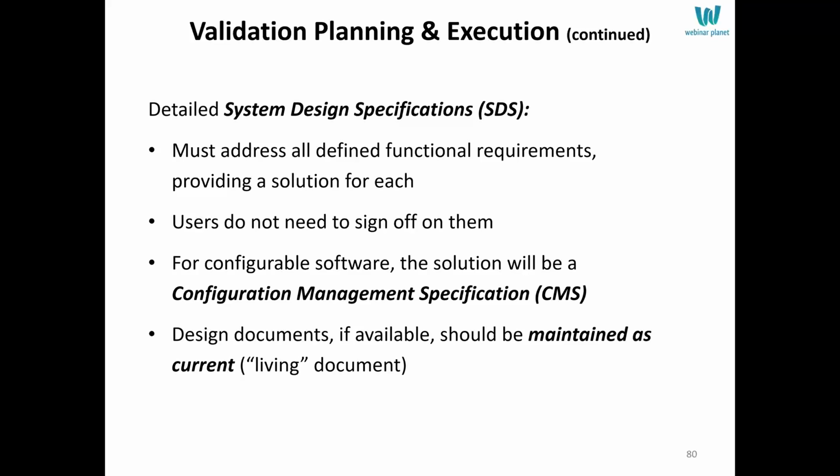But again, you may not have access to these. If the vendor has them, you would want to make sure you state in your validation plan, we asked the vendor, they wouldn't provide these documents. And so by virtue of the fact that once we put the application software in place and test it through OQ and maybe PQ, then we are confirming that the underlying design or configuration settings on the system are correct.